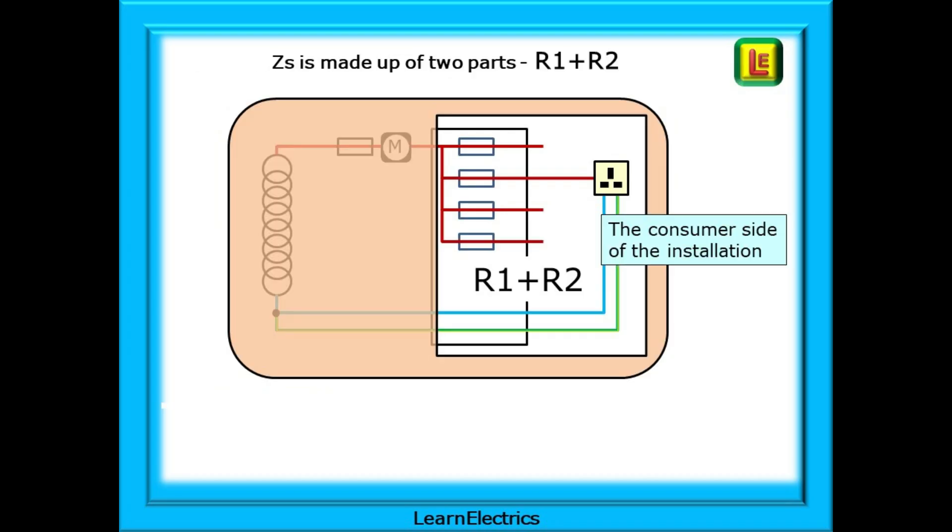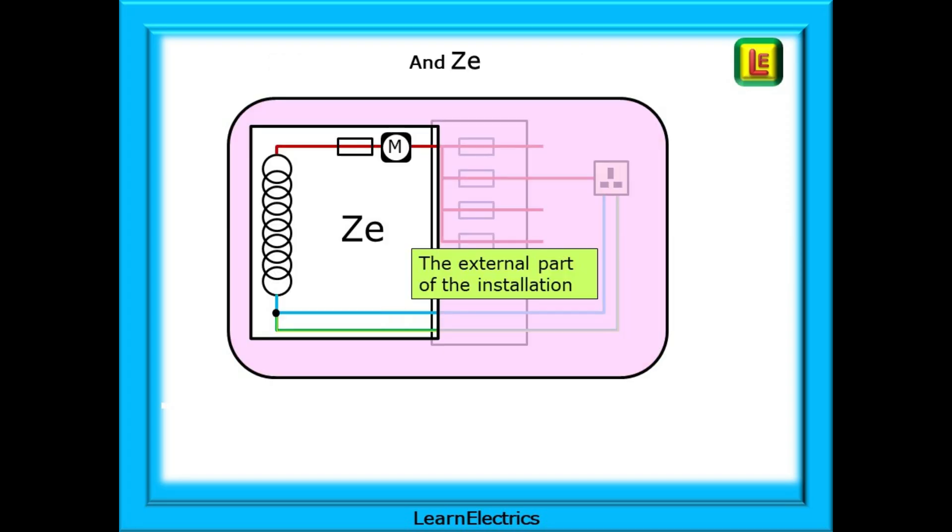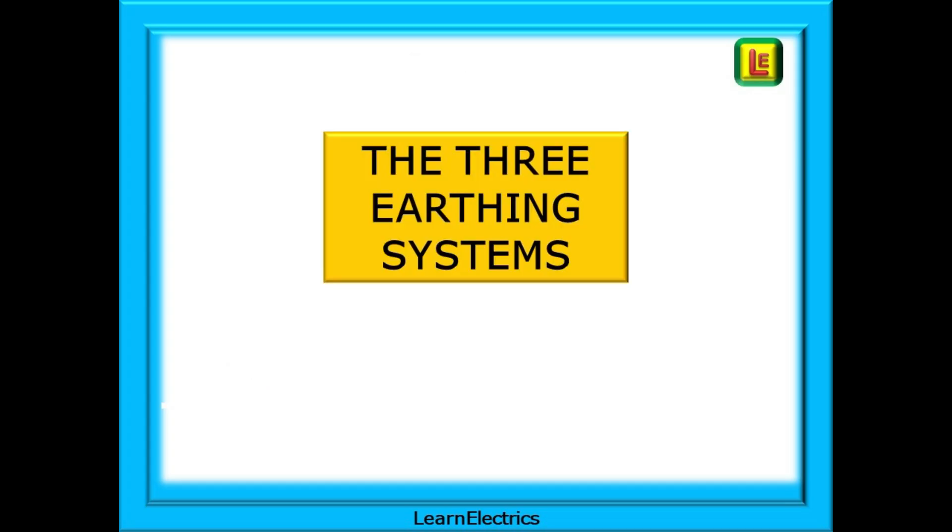ZS, the whole system, the whole circuit, is made up of two parts. The consumer side of the installation, inside the building, from the consumer unit to the points of use. And this is called R1 plus R2. And ZE is the external part of the installation, from the consumer unit all the way back to the supply transformer. Think of ZE, E, as being E for external. So what are the three common earthing systems?